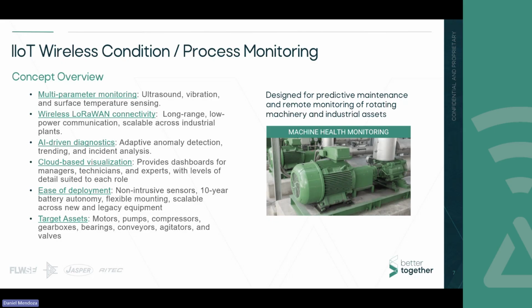We deploy an AI agent. AI in an application like this utilizes a baseline. We'd put a device on a motor or pump, and run it until we have enough data points to turn on our artificial intelligence. From there, AI sets a baseline for the normal operating standards of that pump or motor, and we utilize AI to look for deviations outside that baseline and look for frequency changes.